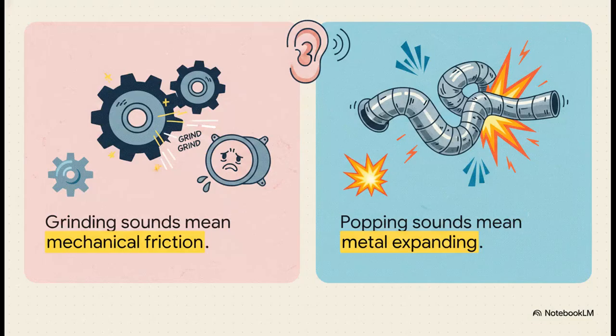And you can actually diagnose some incredibly specific problems just by listening to it. If you're hearing grinding or squealing coming from your unit, you're almost certainly dealing with mechanical friction. That's usually bad bearings in the blower motor, or worse, a compressor crying out right before it completely fails. On the flip side, if you're hearing popping and banging, it's typically an airflow and pressure issue. That's the actual sound of metal ductwork physically expanding and contracting, or loose parts vibrating against the cabinet walls.